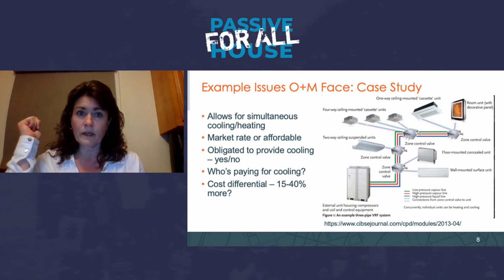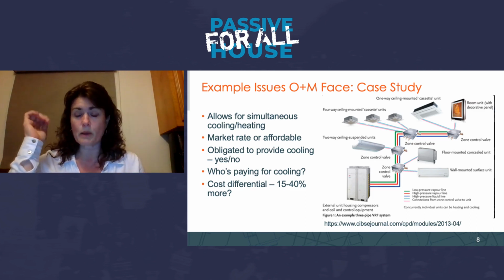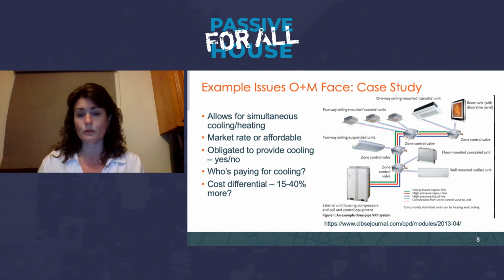Now, one of the issues that we have, especially in affordable projects, is that these systems can be installed two ways. They can be installed with an extra refrigerant loop, which allows you to do simultaneous heating and cooling. So in my apartment, if I need cooling, I can run the AC, but if my neighbor on the north side needs heating, they can run heating. So that's what energy recovery allows you to do in a VRF system.